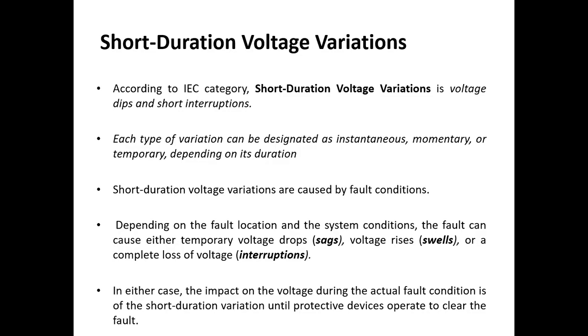The next point we are going to discuss is short duration voltage variations according to the IEC, the International Electrotechnical Commission, category. Short duration voltage variations are voltage dips and short interruptions. Each type of variation can be designated as instantaneous, momentary or temporary depending on its duration. Short duration voltage variations are caused by fault conditions. Depending on the fault condition and the system conditions, the fault can cause temporary voltage drops, called sags, or voltage rises, called swells, or a complete loss of voltage, which is an interruption.